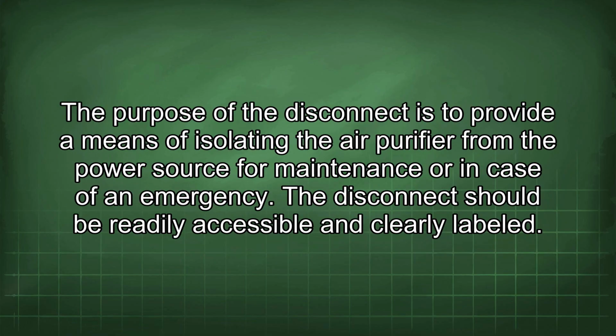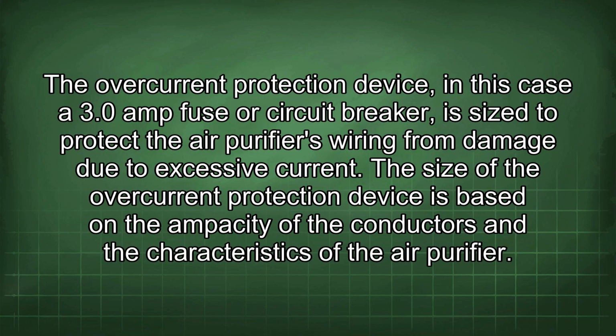The purpose of the disconnect is to provide a means of isolating the air purifier from the power source for maintenance or in case of an emergency. The disconnect should be readily accessible and clearly labeled. The overcurrent protection device, in this case a 3.0 amp fuse or circuit breaker, is sized to protect the air purifier's wiring from damage due to excessive current.